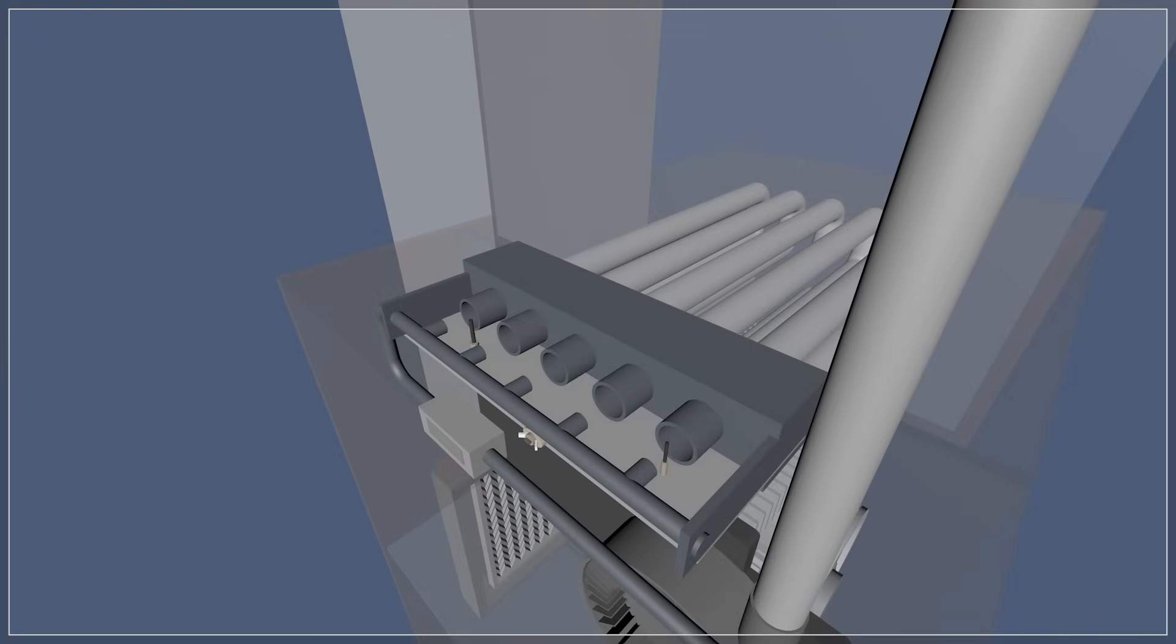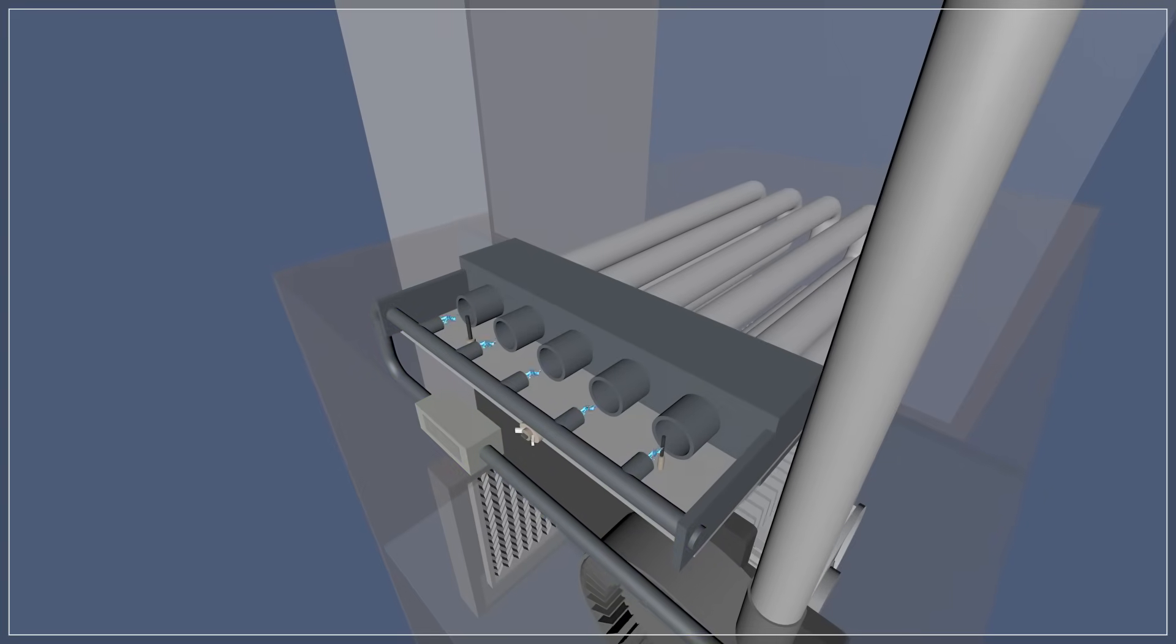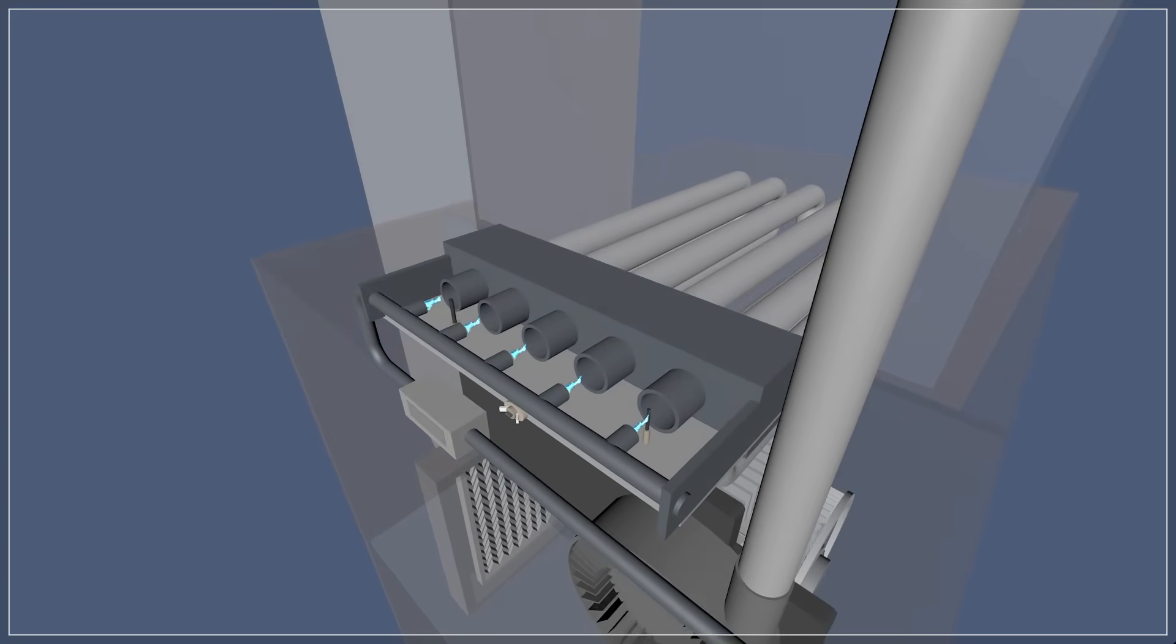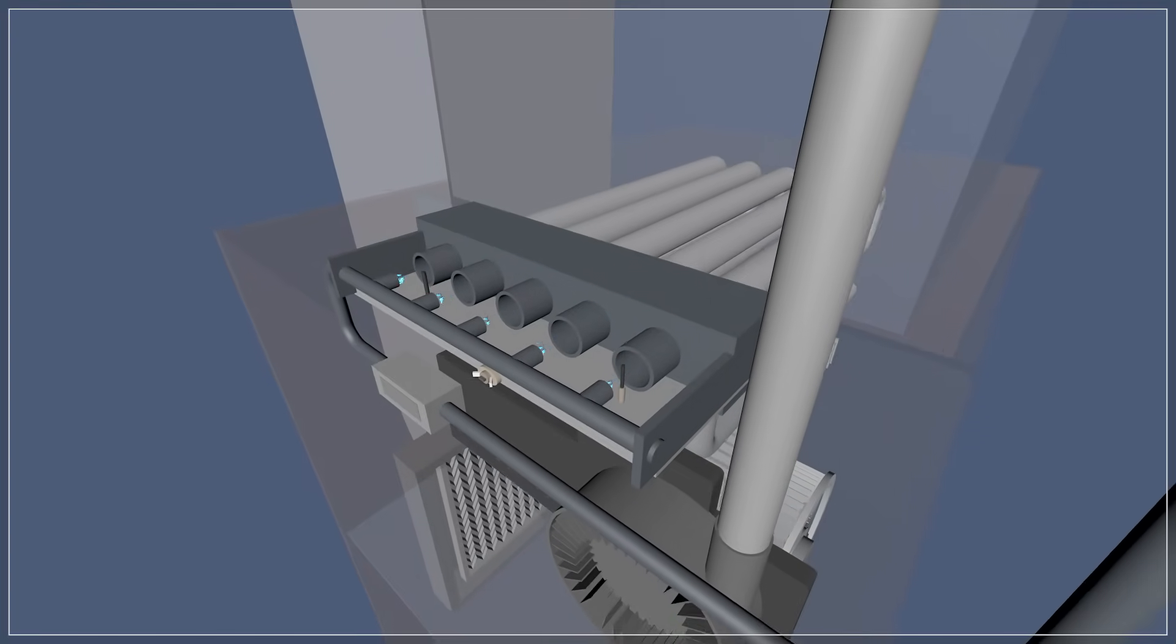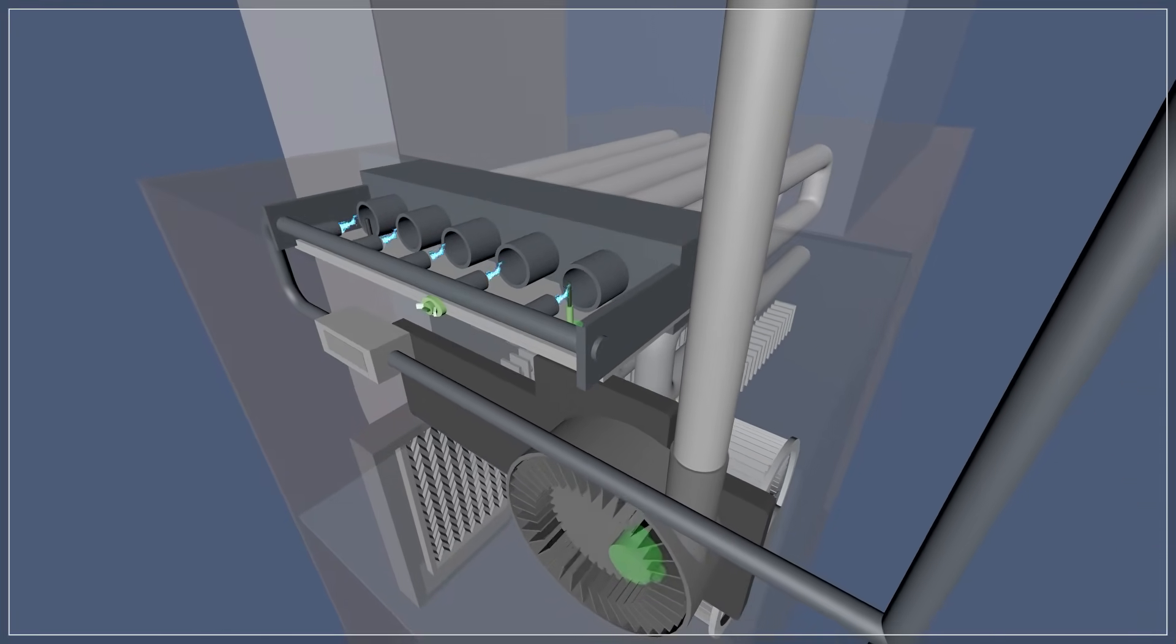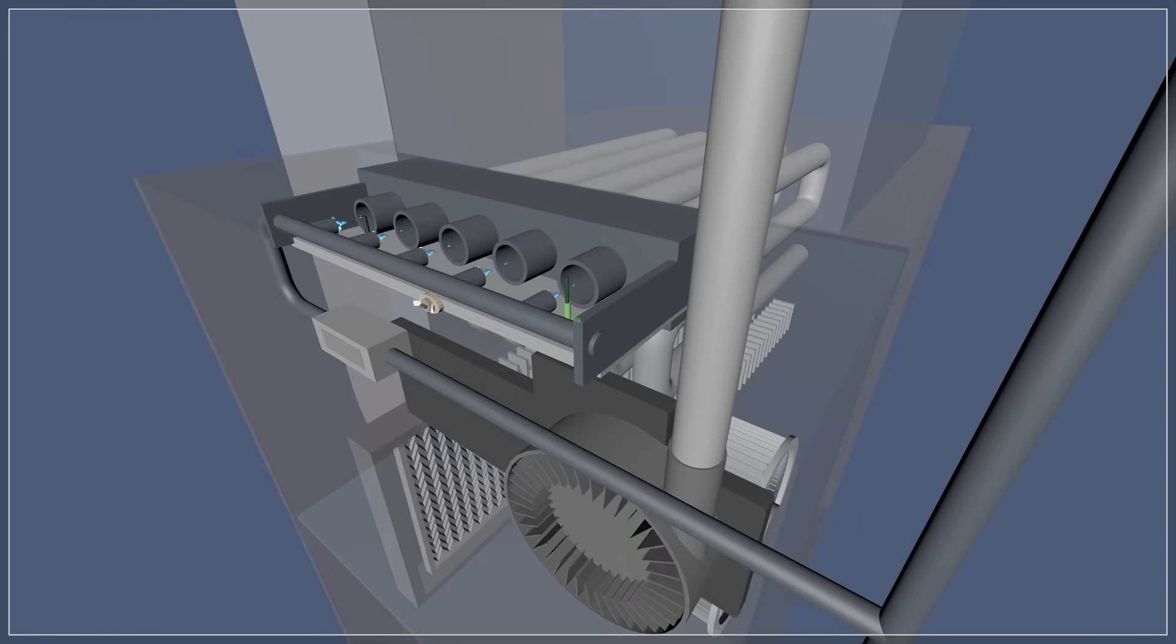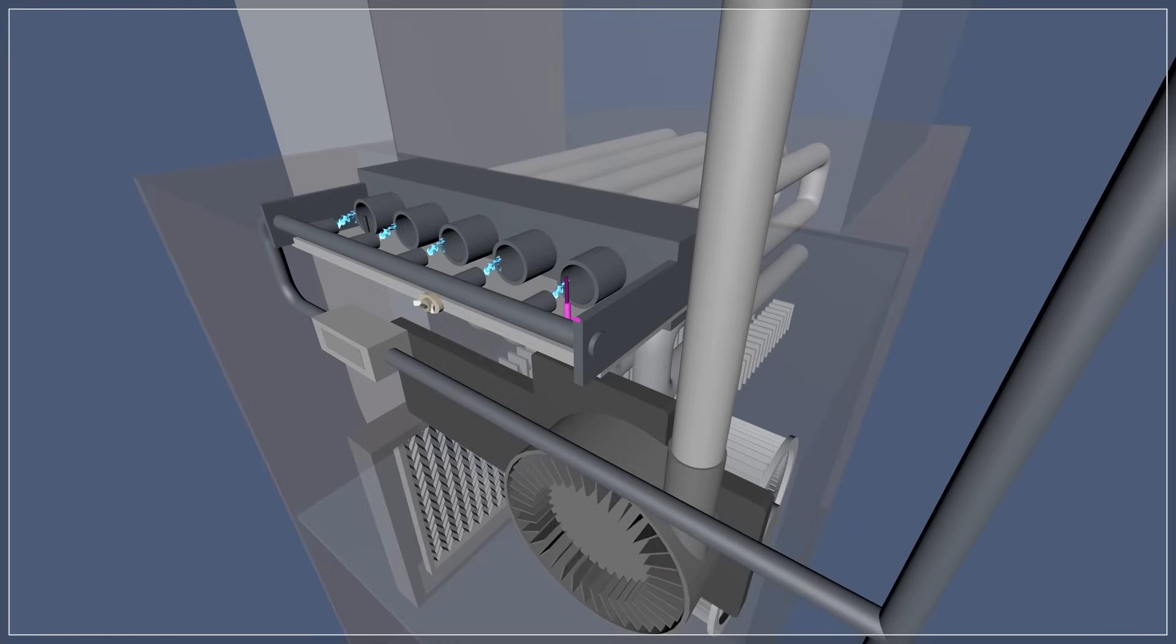If the pressure is good, then voltage is sent to the hot surface igniter. Some furnaces might use a spark igniter instead. After the igniter heats up, the gas valve opens and the burners ignite. The flame will continue as long as the safety switches remain closed. If the flame isn't detected after 7 seconds, the flame sensor will shut off the gas.